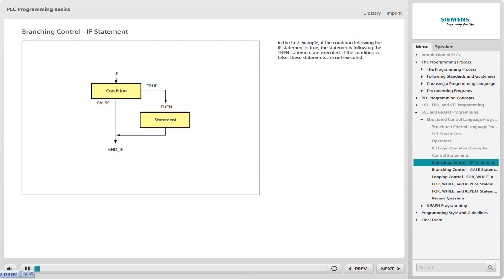An IF statement directs the program execution to one of two branches depending upon whether a condition is true or false. A condition can be simple or complex and can include multiple operators and variables, as long as the condition can be tested as true or false. In the simplest example, if the condition following the IF statement is true, the statements following the THEN statement are executed. If the condition is false, these statements are not executed. Regardless of which branch is followed, the branching is terminated by an END_IF statement.